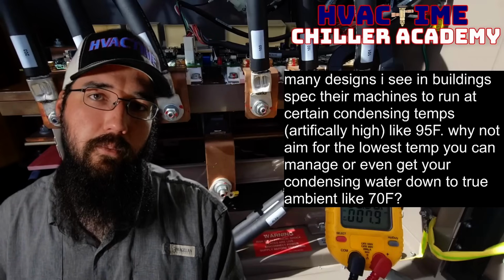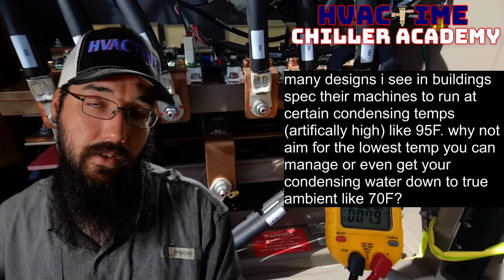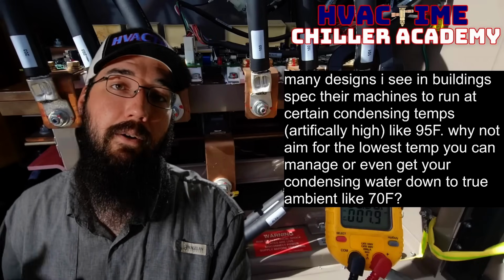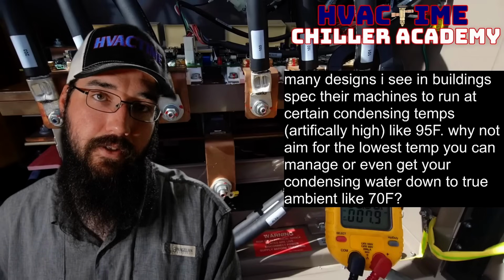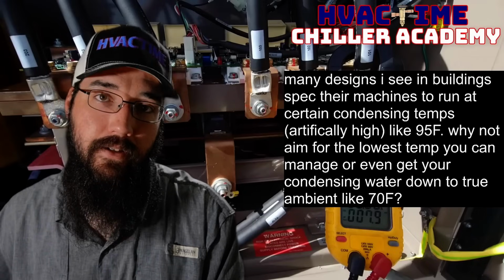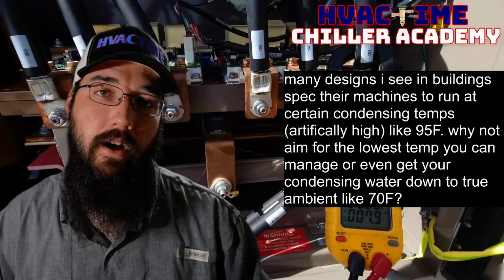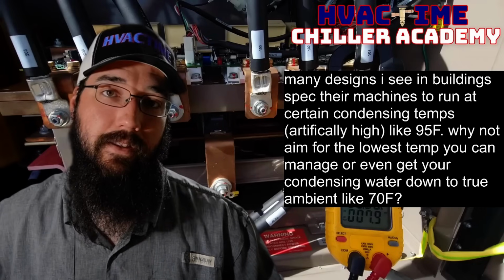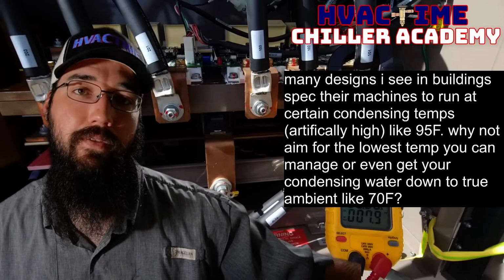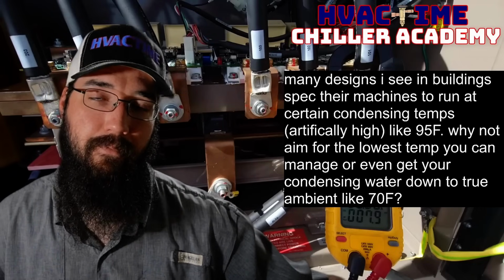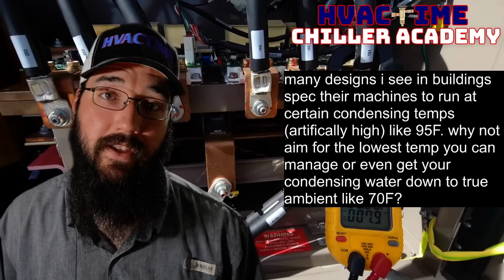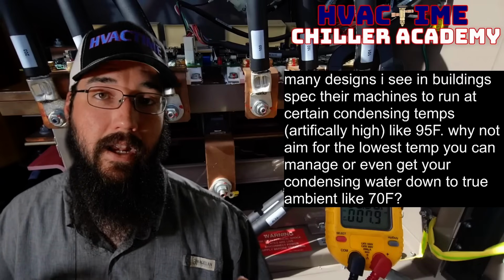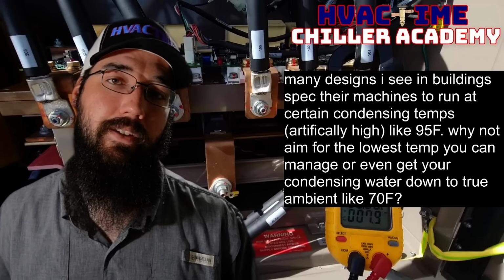Okay, so instead of trying to get it to 78 degrees of saturation on the condenser, now we've got to get it to 88 degrees of saturation. That's a pretty big difference. And that requires 10 amps at the tower fan turns into 50, 60 amps at the compressor. Now, these aren't hard numbers. These are just examples, but this is realistic to what I personally have dealt with in these cases.